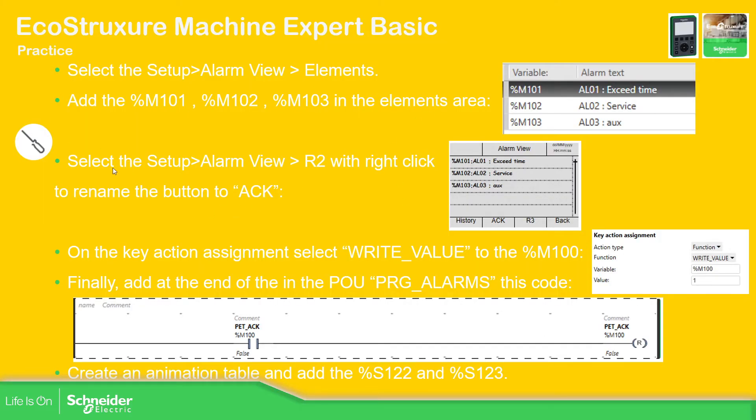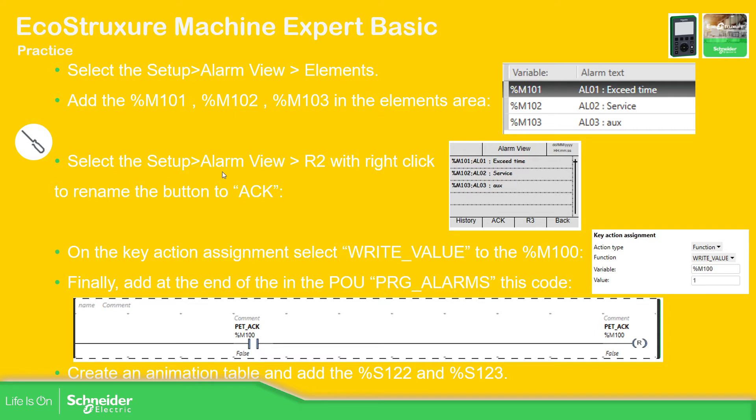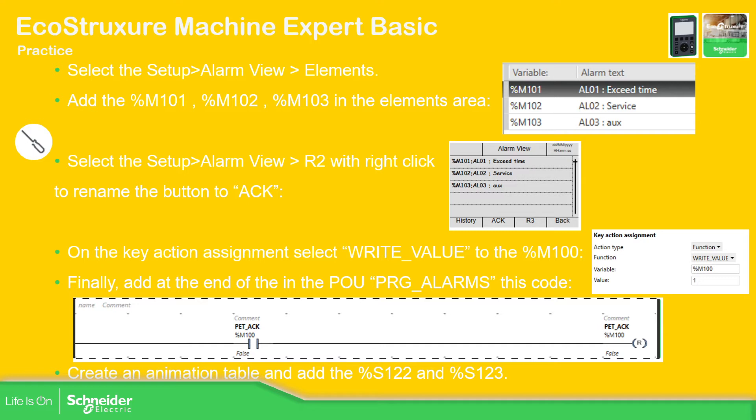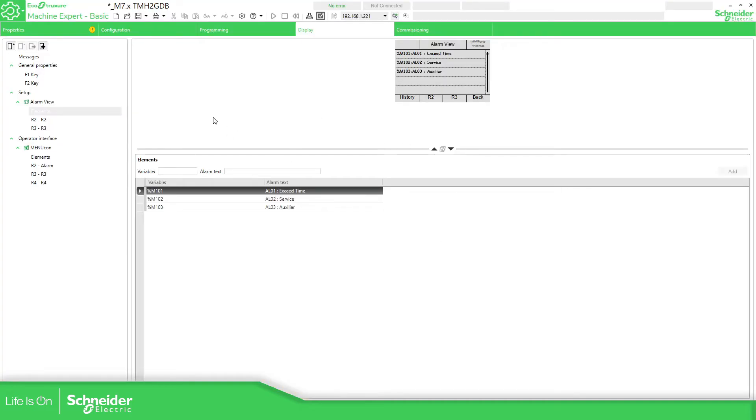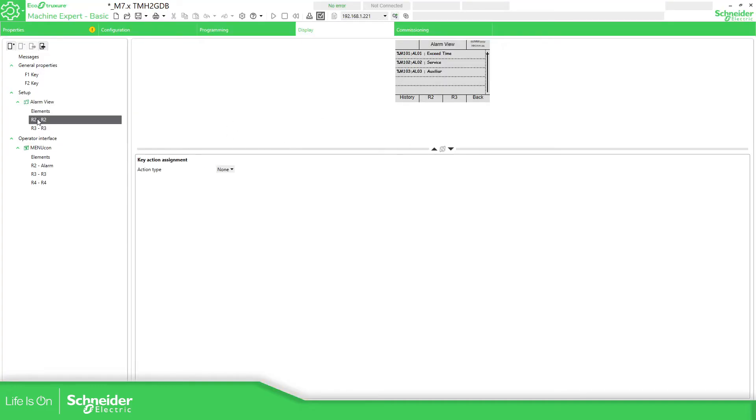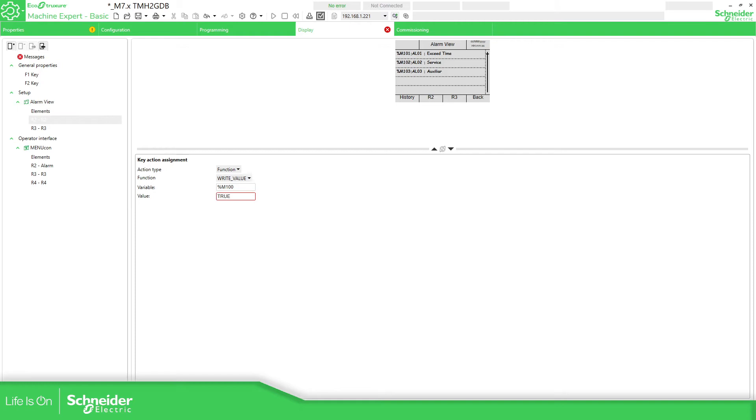So now what we're going to do is to define one of these actions or keys that we have, an action to acknowledge the alarm that we have. So I'm going to use an additional variable M100 to acknowledge that, and I'm going to add this code at the end of the PRG alarms. So let's go to the application. R2, I'm going to specify function, write value, value, variable %M100, value true, 1.